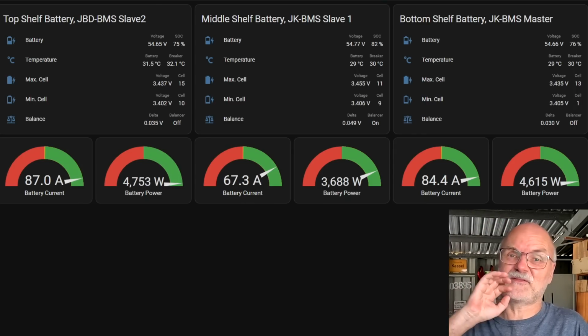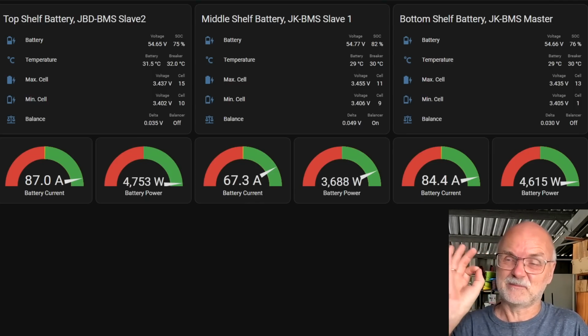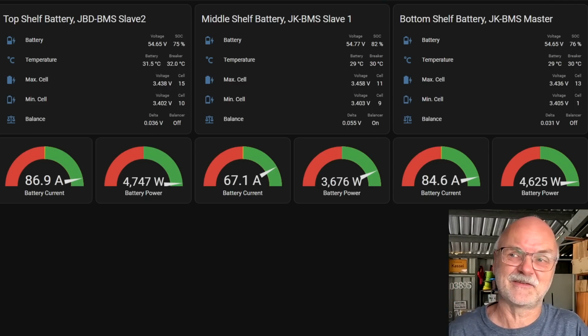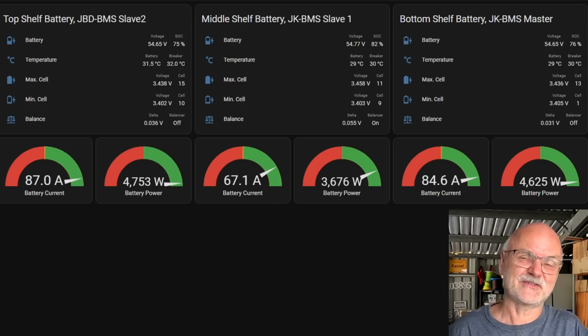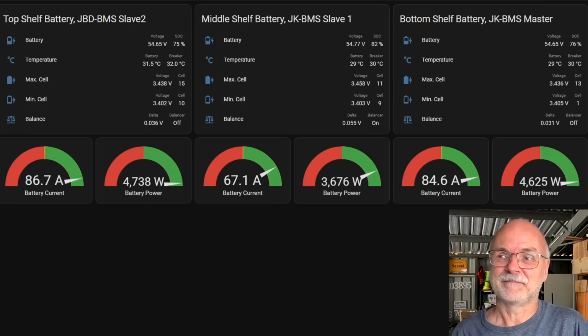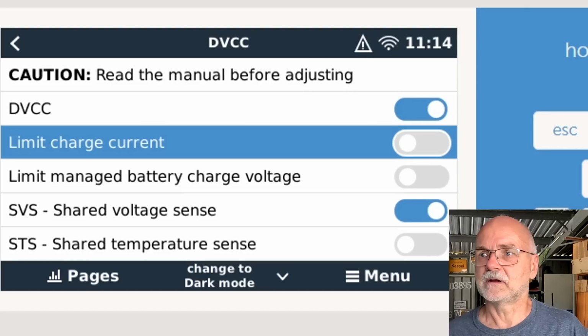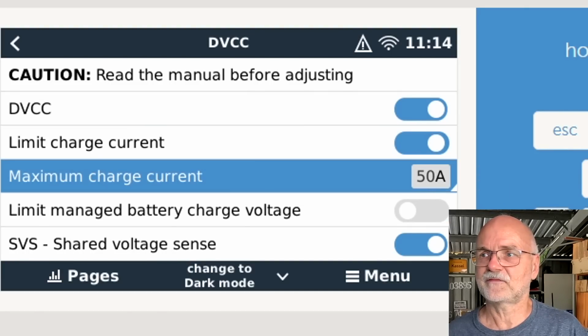This is exactly what we've seen a lot of times when testing parallel batteries. The middle shelf battery was always late to the party - late discharging, late charging. This has been the situation since we installed the battery shelf, and there was never a problem with it. The middle shelf battery charges and discharges at the same rate as all the other batteries, it's just later. Okay, set the charge limit again, say 100 amps for now.